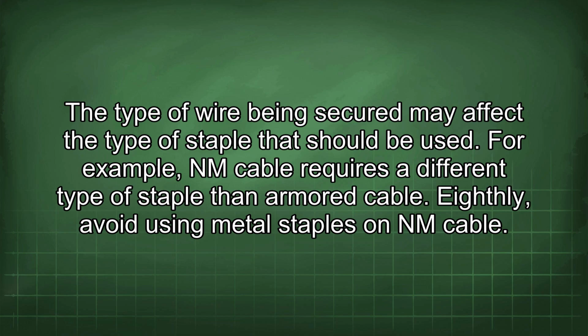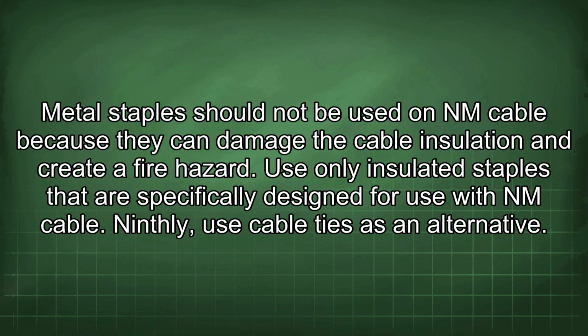Eighthly, avoid using metal staples on NM cable. Metal staples should not be used on NM cable because they can damage the cable insulation and create a fire hazard. Use only insulated staples that are specifically designed for use with NM cable.